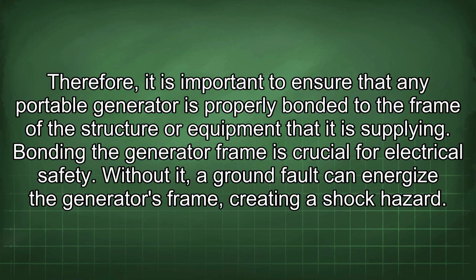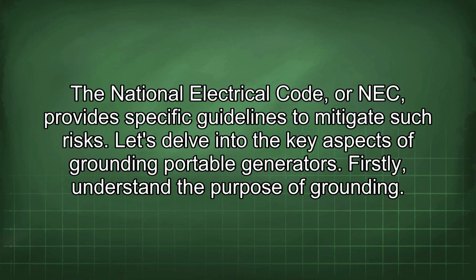Without it, a ground fault can energize the generator's frame, creating a shock hazard. The National Electrical Code, or NEC, provides specific guidelines to mitigate such risks. Let's delve into the key aspects of grounding portable generators. Firstly, understand the purpose of grounding.